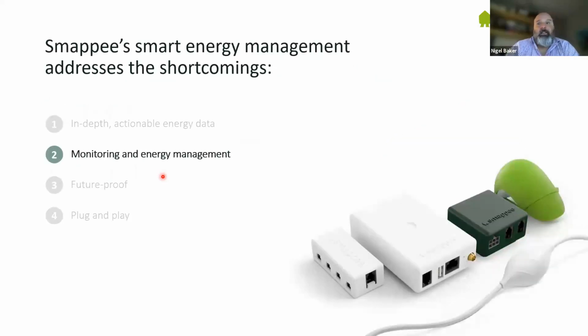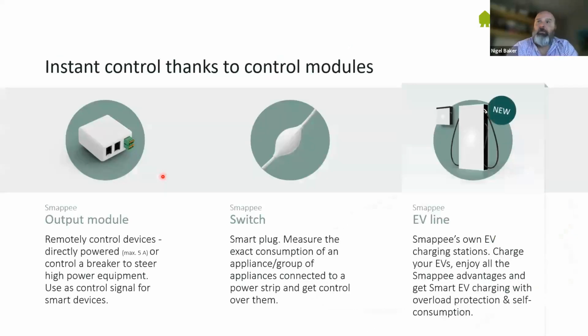On the monitoring and energy management side, where you want to actually manage your energy, we've got hardware to control your energy flows, breakers, or contactors. We have an output module, a 5 amp output which you can connect through any contactor, motorized breaker, or shunt trip, to switch any contactor on and off. So you can shed or switch on any load, as long as it goes through a contactor, since we connect into the control signal of the contactor.